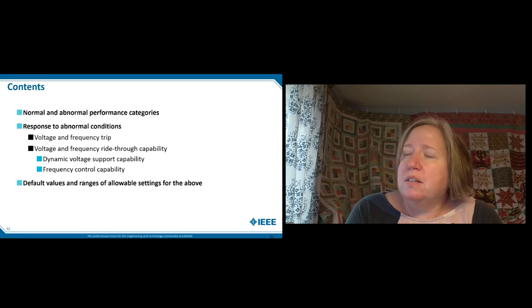So, ride-through is really a response to the potential for widespread DER tripping. System frequency is defined by the balance between load and generation. It is similar across an entire interconnection. So I'm in WECC, so the frequency across WECC is the same. And so one big frequency deviation could start dumping all of the DER on the system, and that could start causing problems in a number of places, including here at Portland General Electric. So that's not good. And because this impacts all the DER, whether it's high penetration or low penetration, it can all come off.